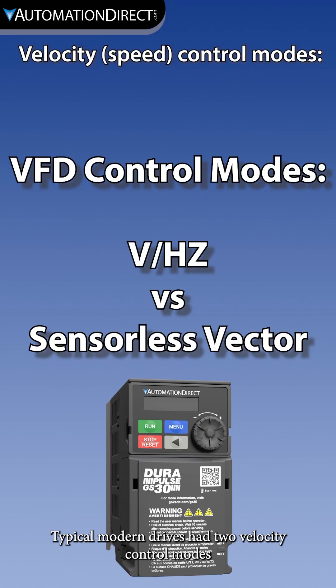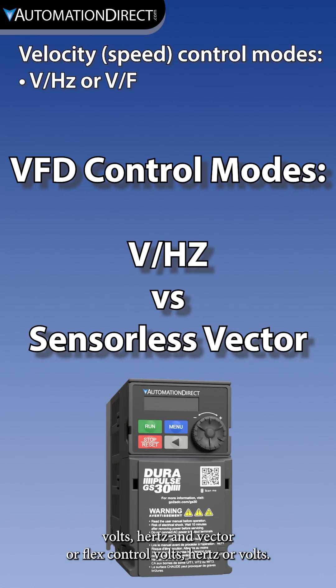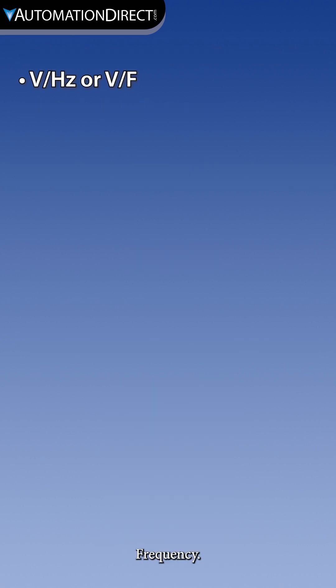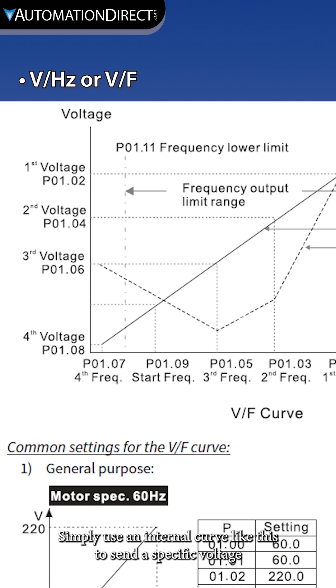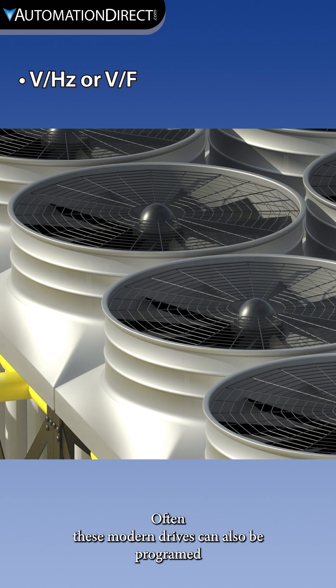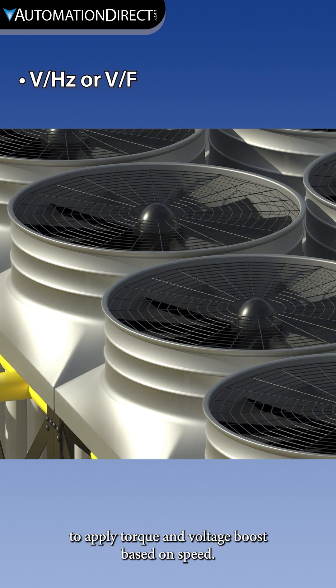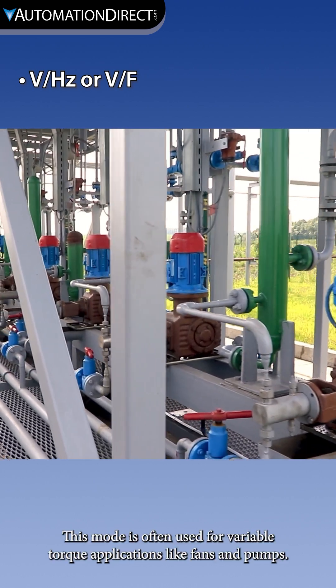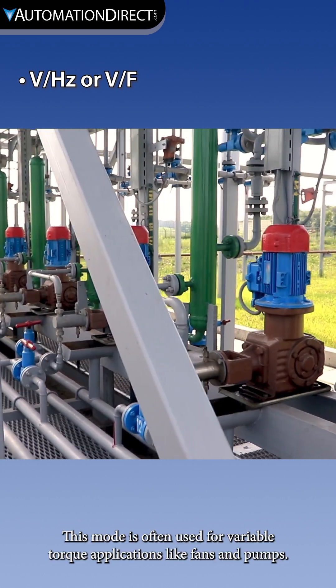Typical modern drives have two velocity control modes: volts-hertz and vector or flux control. Volts-hertz, or volts-frequency, simply uses an internal curve like this to send a specific voltage and frequency to the motor based on the speed command. Often, these modern drives can also be programmed to apply torque and voltage boost based on speed. This mode is often used for variable torque applications like fans and pumps.